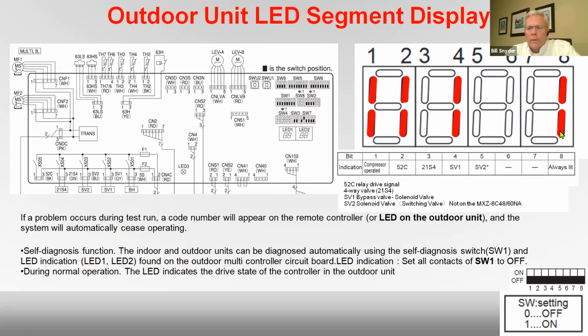Right now they're telling you that number 8 is on, which should always be lit. Basically it means there's power to the unit. Of these other three, the first one means that the compressor is operating. The second one means 52C is working, so that means the relay drive signal that drives the compressor is made. And the fourth one is service valve 1, or bypass solenoid valve. It's a solenoid valve 1. So I believe that's when it's made, it's in the cooling mode. Okay, so that's one way these things work.